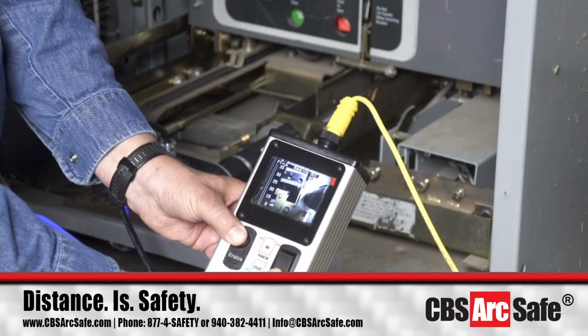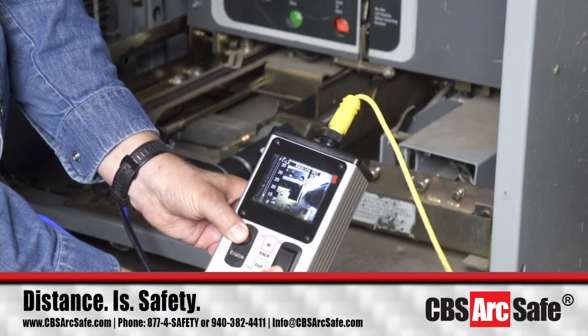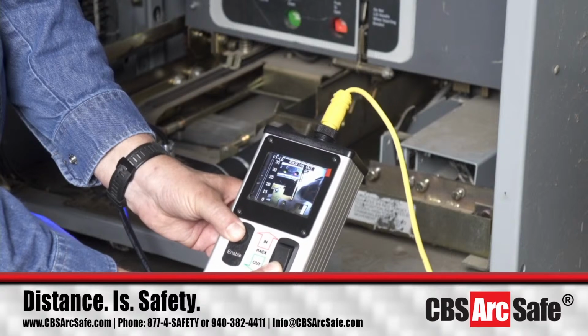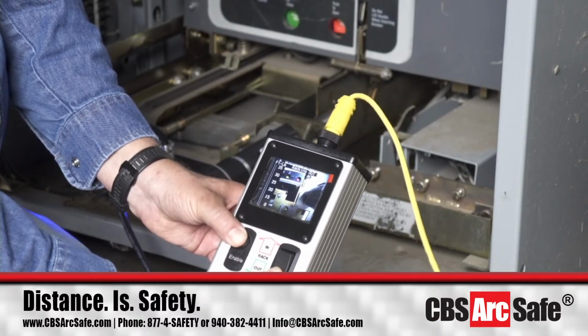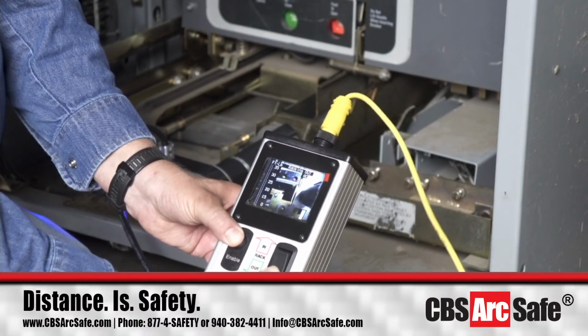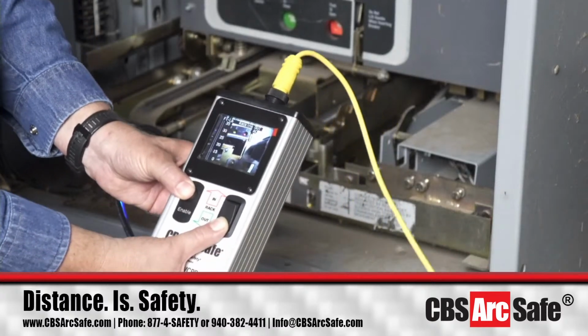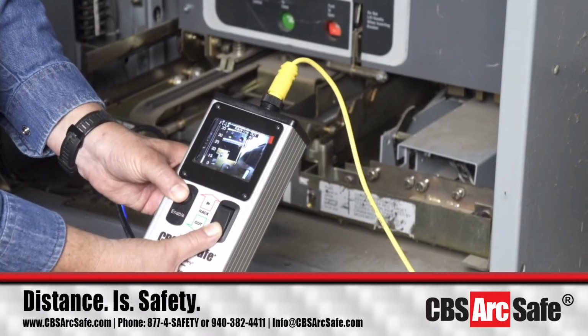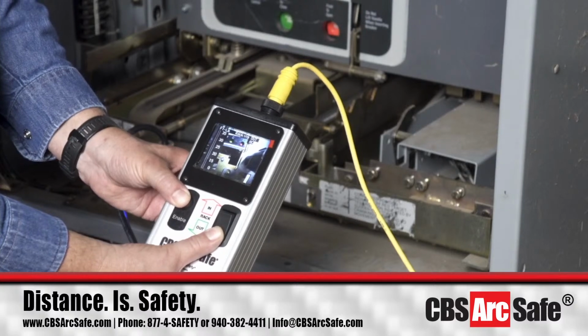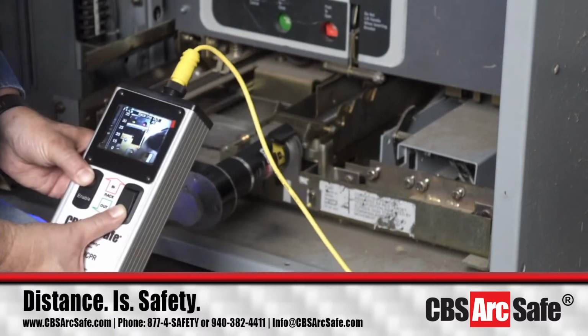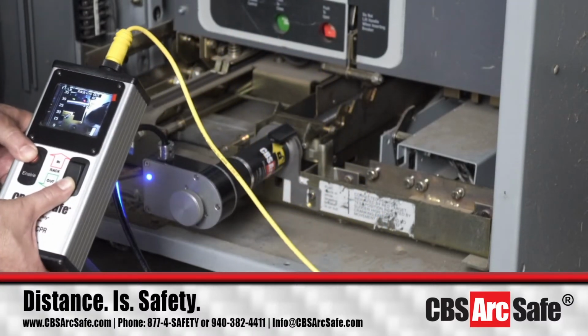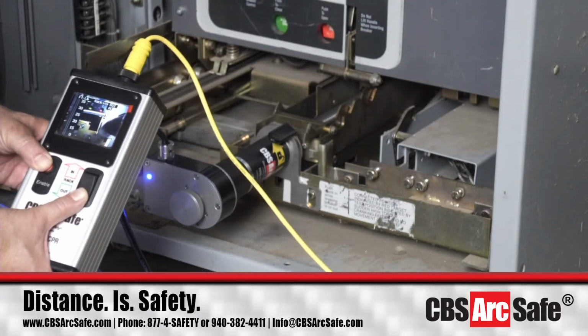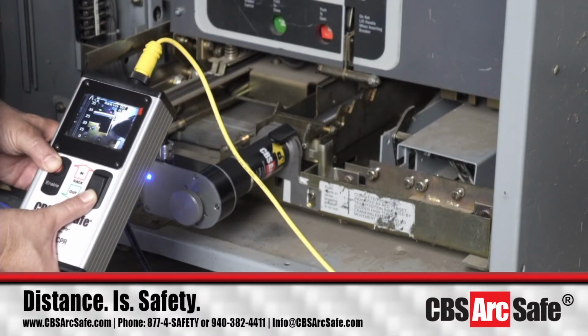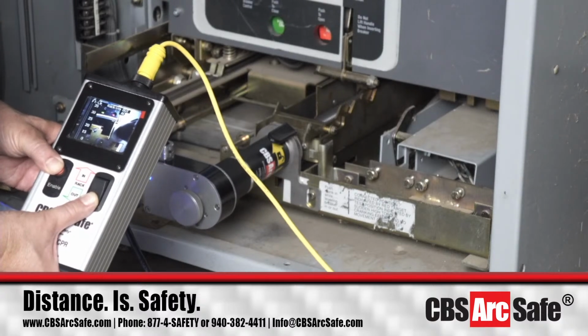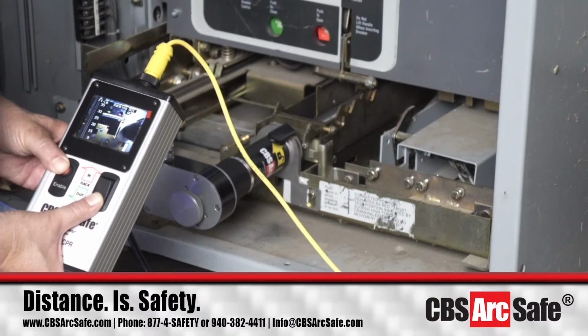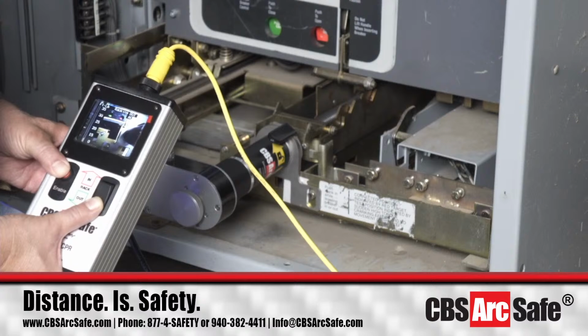One of the things to understand is this thing isn't made to go fast, okay? That's the basic design of the switchgear itself. It's made to be racked at the rate that a man racks the breaker. If you try and go faster than this, you can destroy switchgear. So that's one of the things to understand: we design things to operate at the rate a man does things, just so we keep things safe and also preserve the equipment.